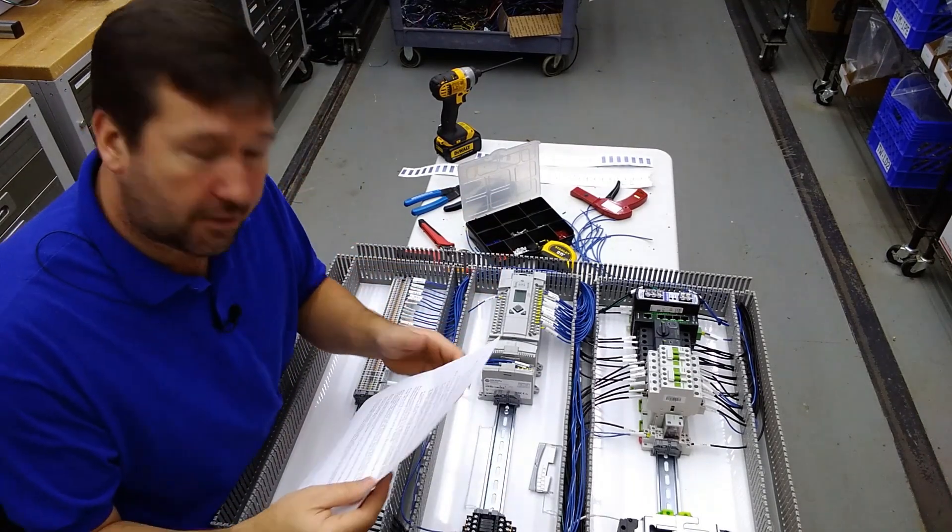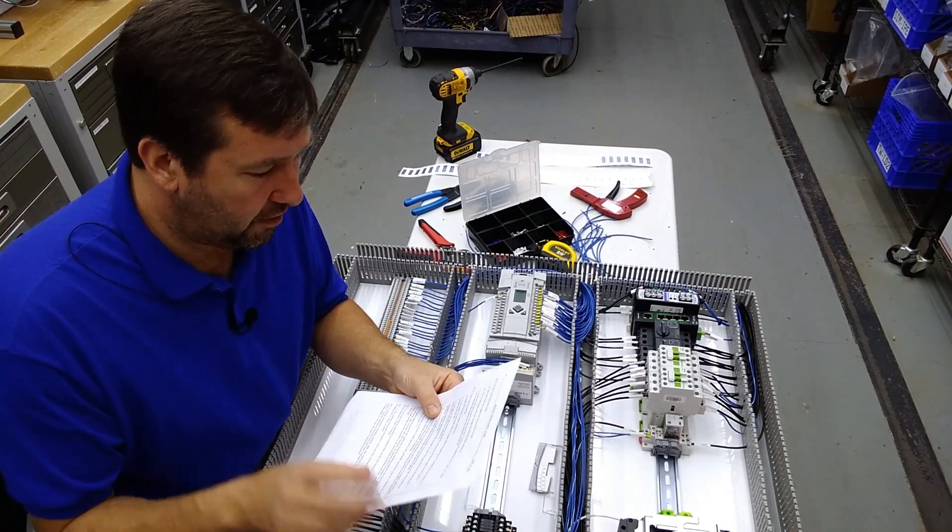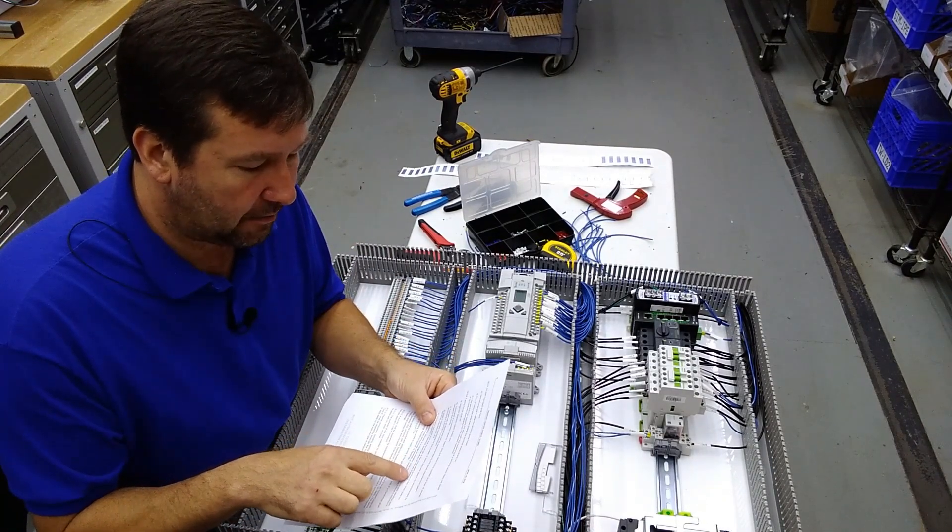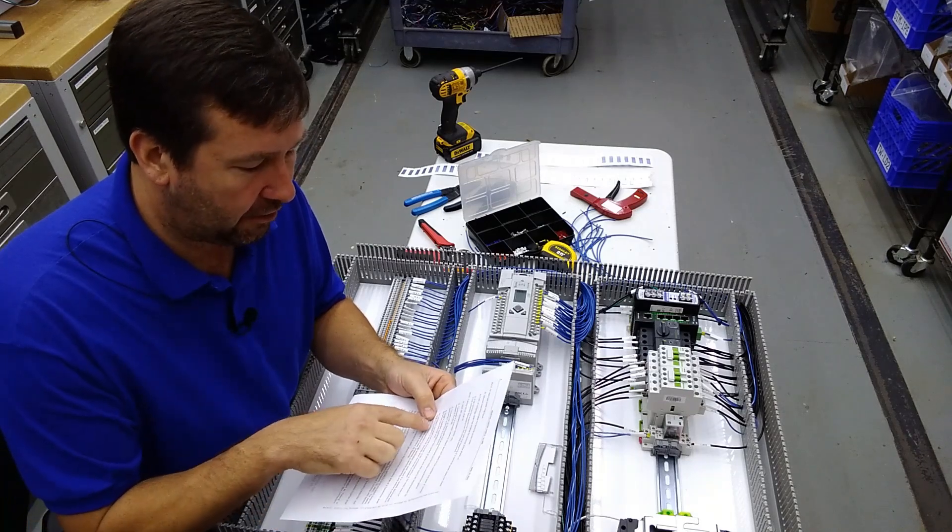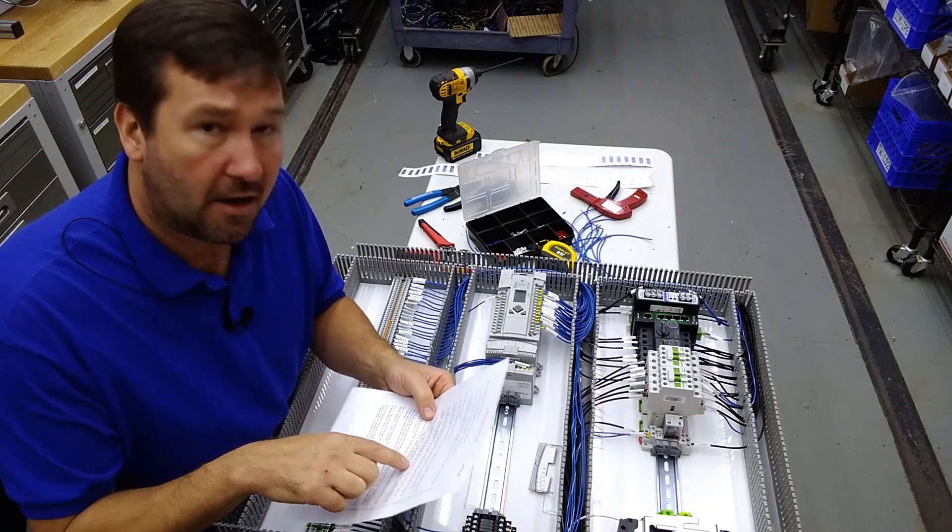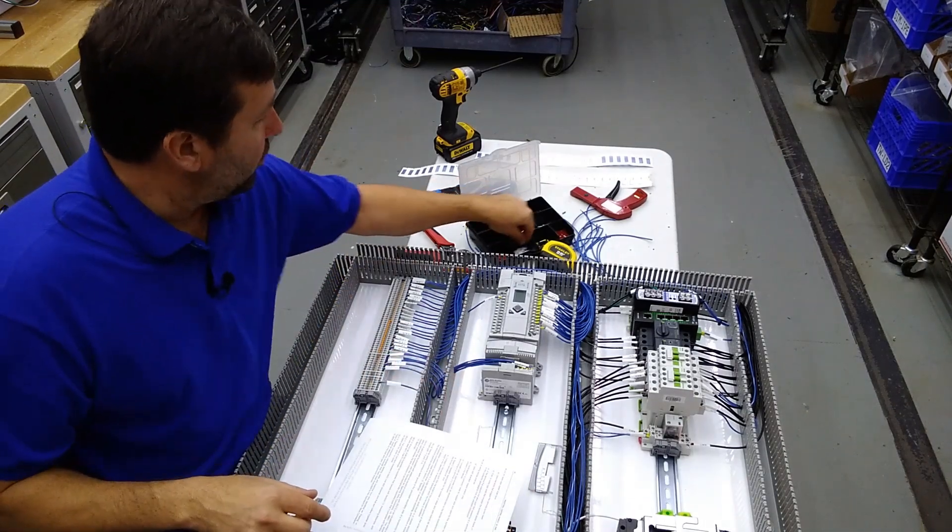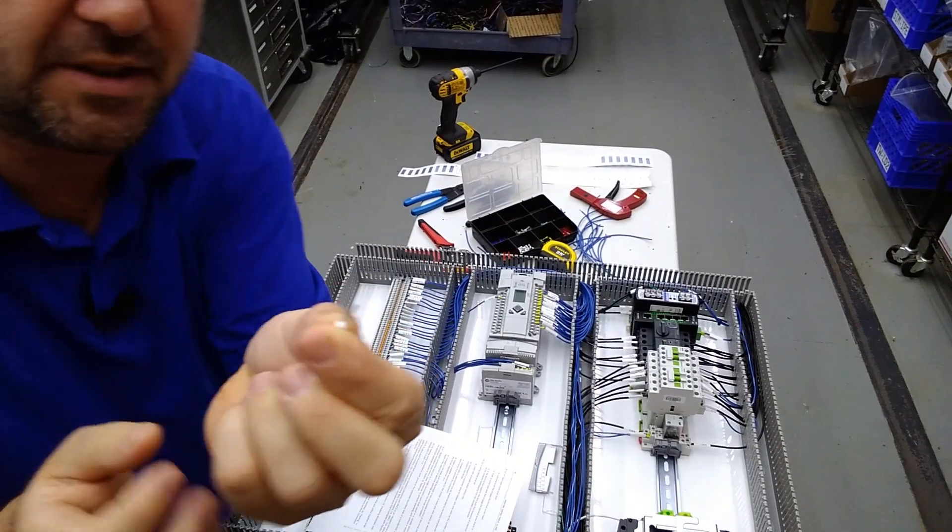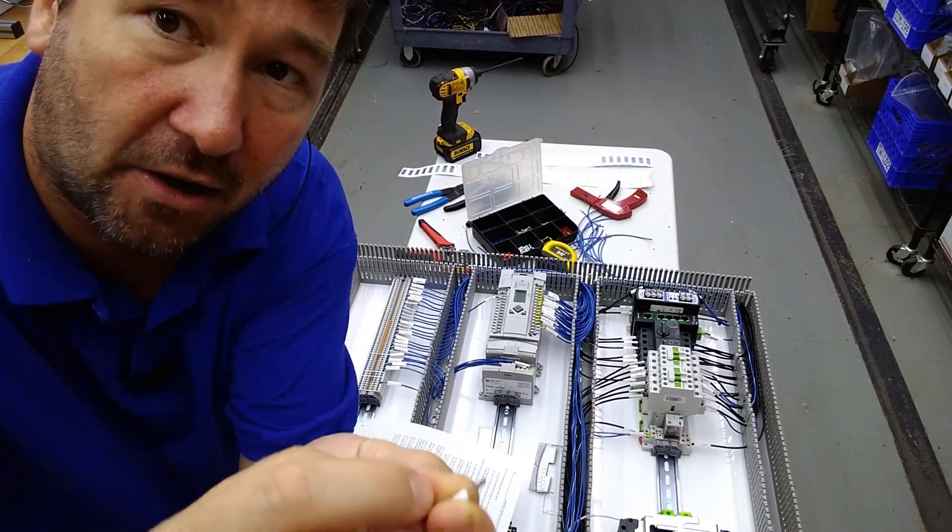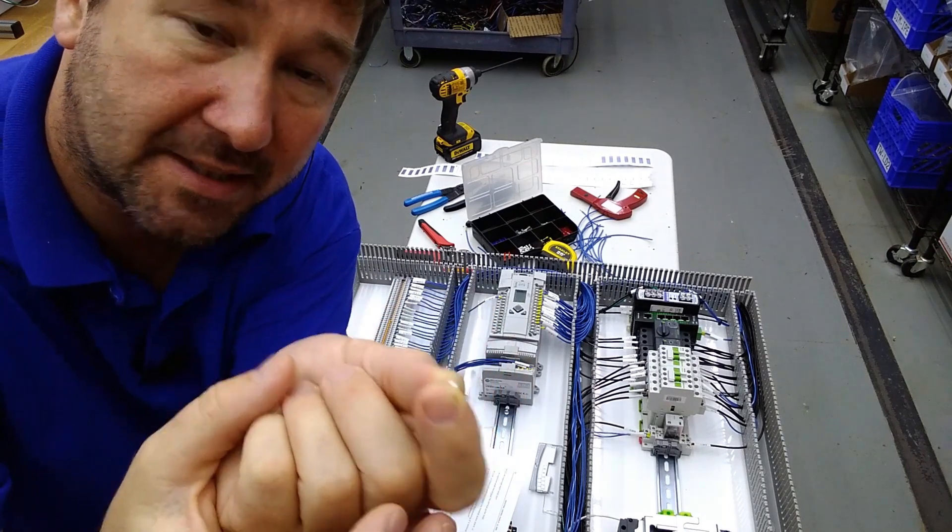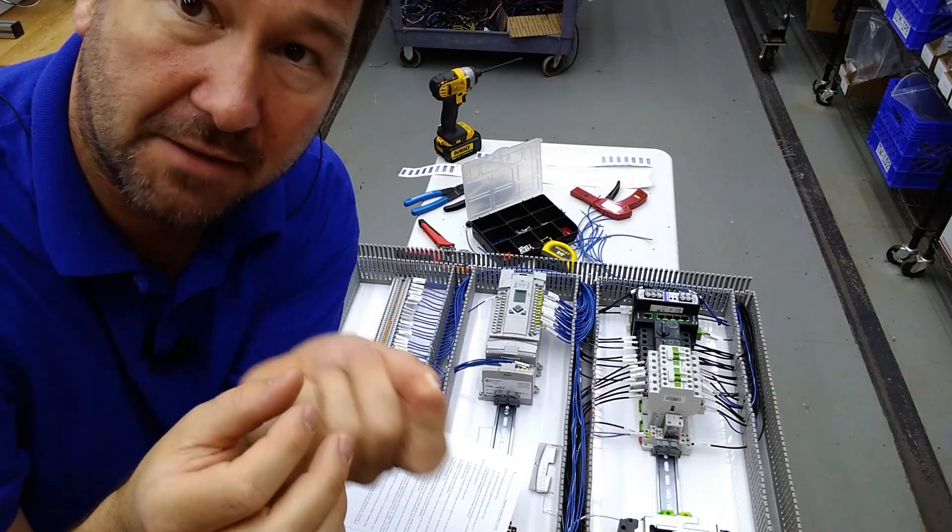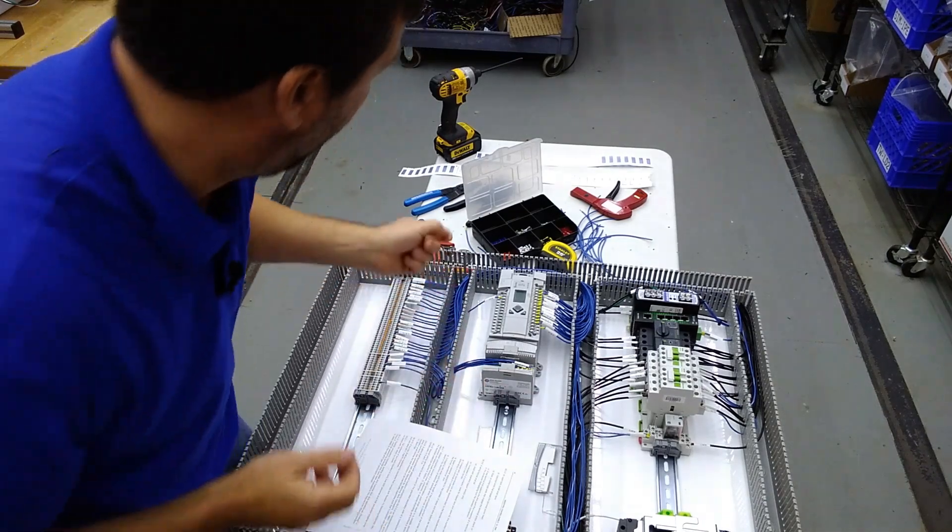And then here's another big one: 'crimped to the wires in such a length that the uninsulated portion of the wire does not result in a reduction in electrical spacings when the ferrule is installed.' So for example, if I'm using this ferrule right here which is about three-eighths long of exposed conductor, I can't put this into something that requires one inch of exposed conductor. I would need a longer ferrule for that.